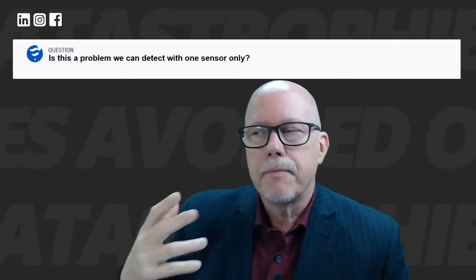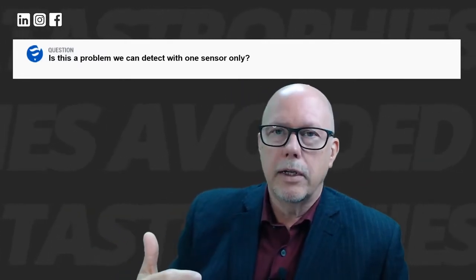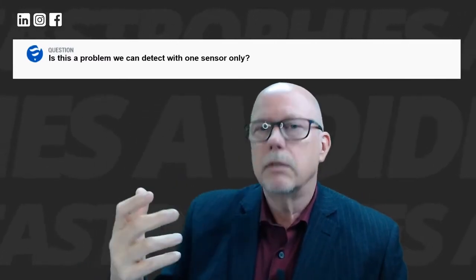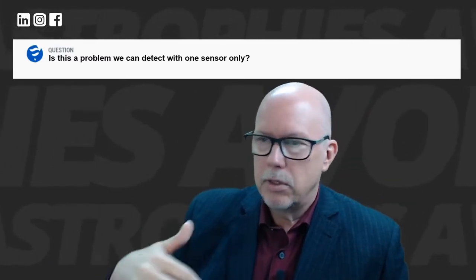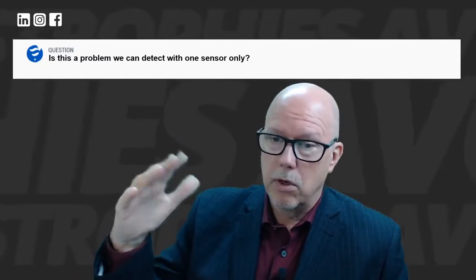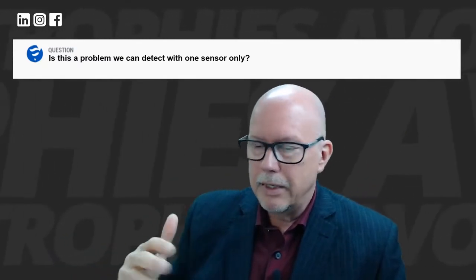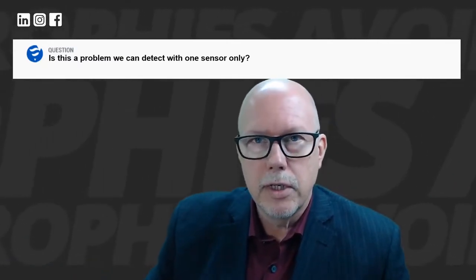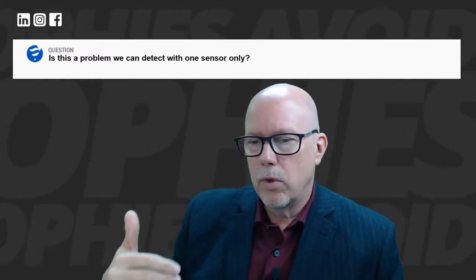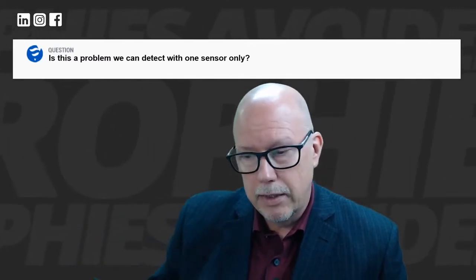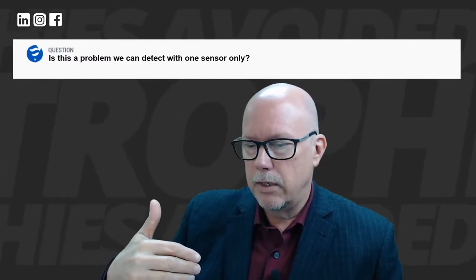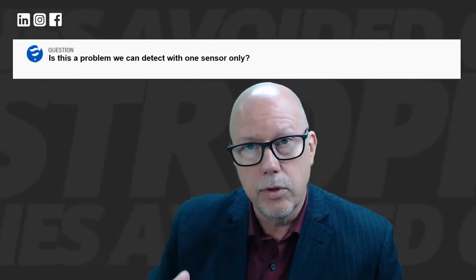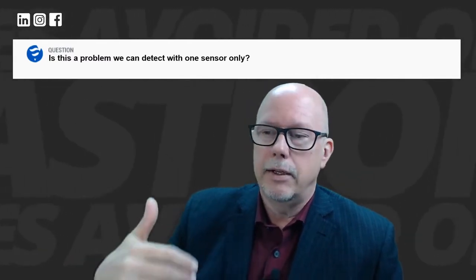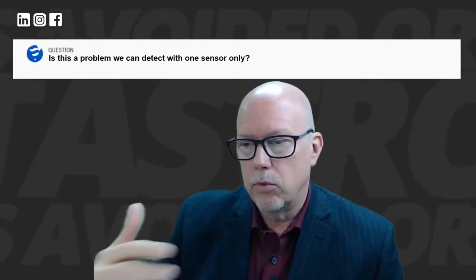So yes, you can look at rotor movement using one air gap sensor. If you have a tall rotor, we strongly recommend you put sensors top and bottom. But if you're going to put sensors in to look at a rotor problem, why not put sensors all the way around like they did, giving you a chance to look not only at the rotor but also at the stator? There's a lot of dynamics involved between the rotor and stator.